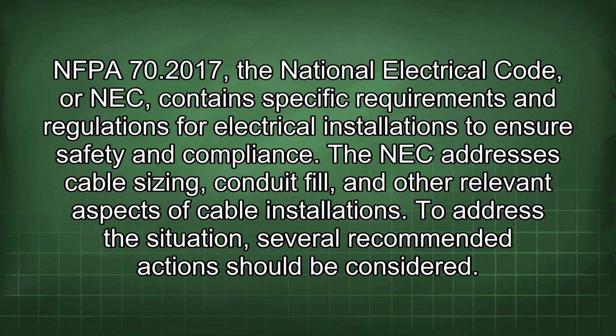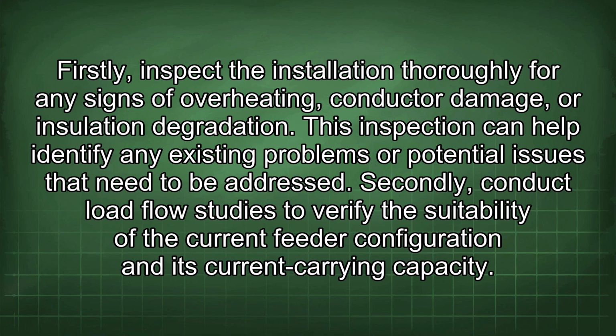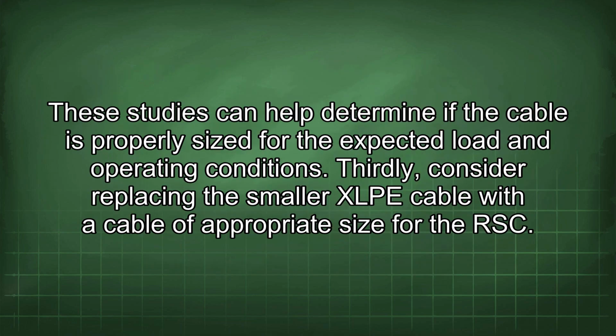To address the situation, several recommended actions should be considered. Firstly, inspect the installation thoroughly for any signs of overheating, conductor damage, or insulation degradation. This inspection can help identify any existing problems or potential issues that need to be addressed. Secondly, conduct load flow studies to verify the suitability of the current feeder configuration and its current carrying capacity. These studies can help determine if the cable is properly sized for the expected load and operating conditions. Thirdly, consider replacing the smaller XLPE cable with a cable of appropriate size for the RSC.